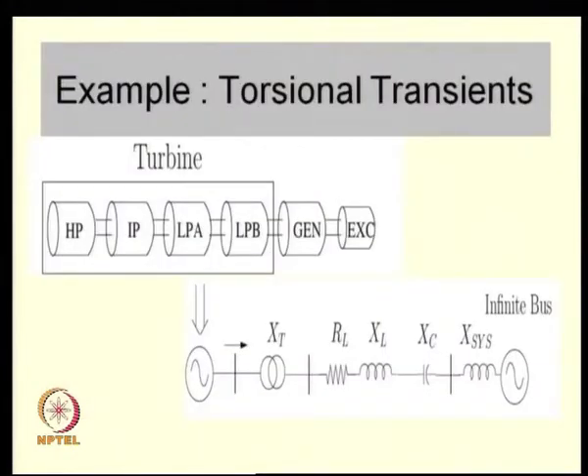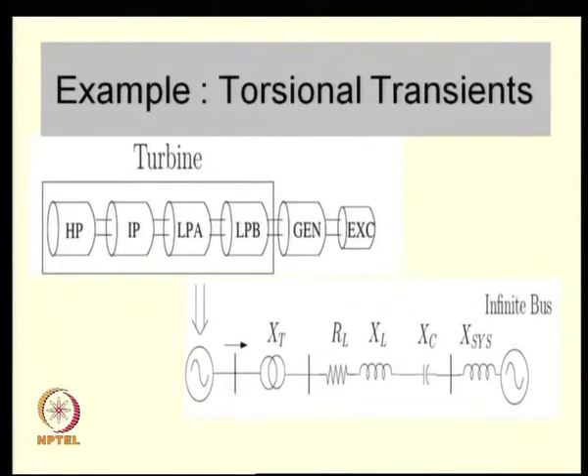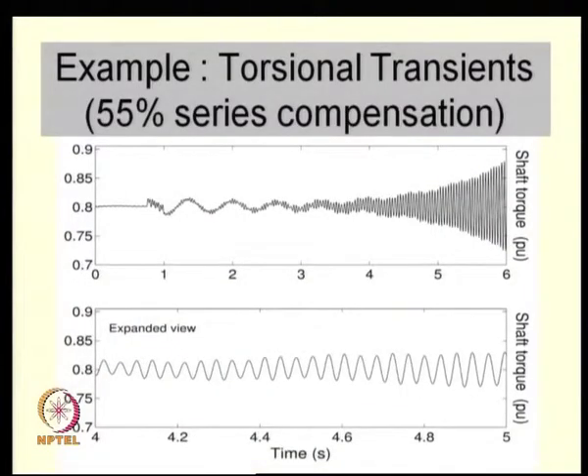In the previous example where we studied sub-synchronous resonance, we considered the adverse interaction of a series-compensated transmission network on the shaft of a generator-turbine system. We did a case study of a steam turbine generator where the rotor was represented by a six-mass system connected by shafts. We saw that for a certain level of series compensation, there was adverse interaction and growing oscillations of one particular torsional mode.